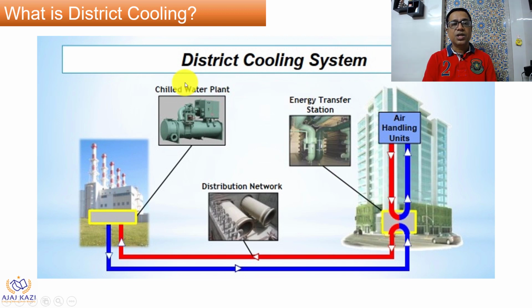This plant generates cold water. There is a distribution network of pipes and pumps, and at each building you will have an energy transfer station that caters to the air handling units or fan coil units of that building. These units then cool the entire building wherever necessary. So air conditioning is taken care of by these low-side equipments called air handling units, for which chilled water is supplied through a heat exchanger, generally called an energy transfer station. This is how cooling demands are taken care of - in a nutshell, this is district cooling.